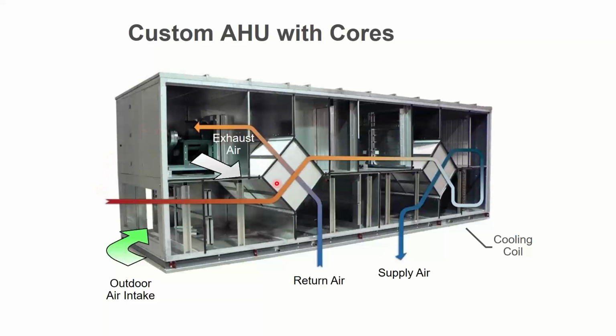The fresh air came in, picked up whatever BTUs it needed. It comes through here, and then it drops off some BTUs in this heat exchanger, goes into the cooling coil and gets subcooled, wraps back around itself, and picks up the BTUs that it had left. So instead of subcooling and then reheating to temper it back up to a neutral temperature, which is no longer allowed by code, unless you get the reheat from a free source, here's your free source. This is one way to do it.